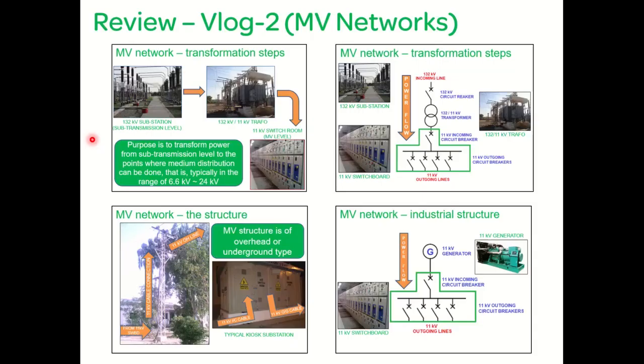First, a review of our last vlog which was related to the medium voltage networks. We discussed how the power at sub-transmission level is converted into medium voltage level using a power transformer, and then power reaches the medium voltage switchgear. This conversion process is done in the high voltage substation, and the medium voltage level used is from 6.6 kV to 24 kV — however, this voltage level can go up to 40 kV. Power from the HV substation is further distributed either using overhead lines or through underground cables.